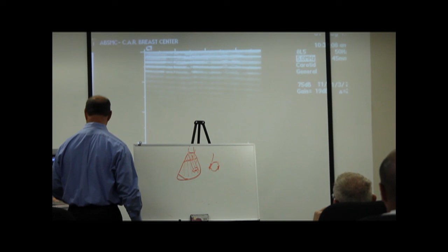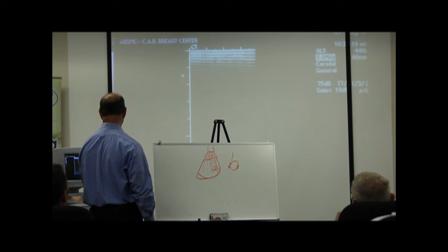This isn't quite squared up for some reason, but our frame rates are right up over here in the corner. And so you can see when I try to do more with an ultrasound image, meaning if I'm going to be shallow, I can run at 52 hertz. If I really want to scan deep, it's going to take longer to get the sound down there and back. My frame rates are going to go down. If I want to use color, again, I'm going to task the machine, and it's going to give me even slower frame rates because I'm doing more information.